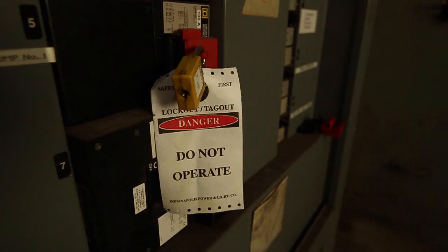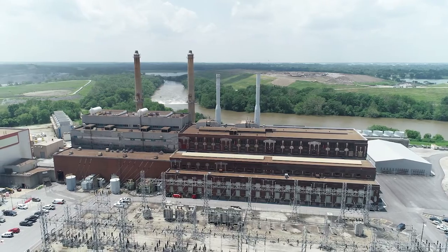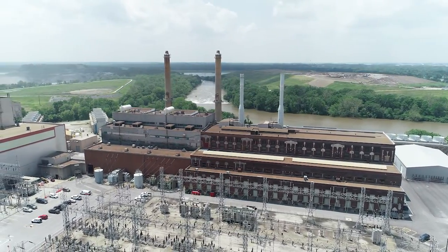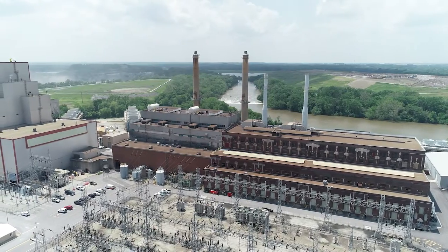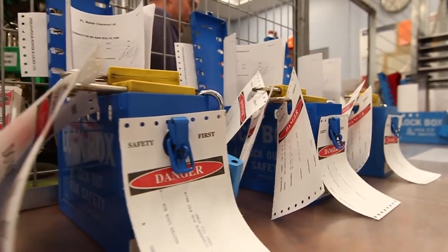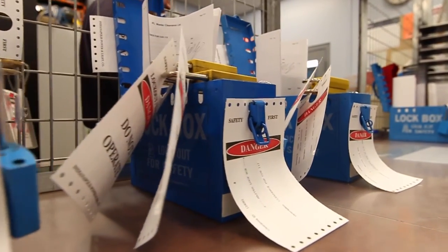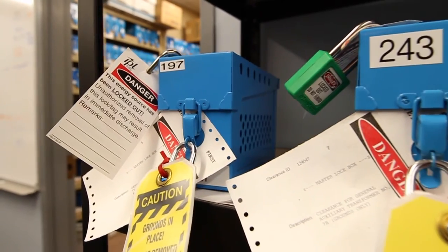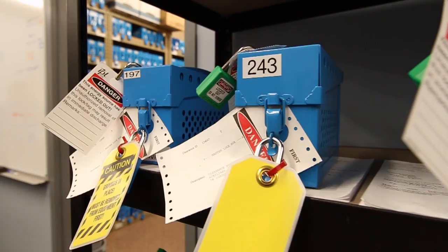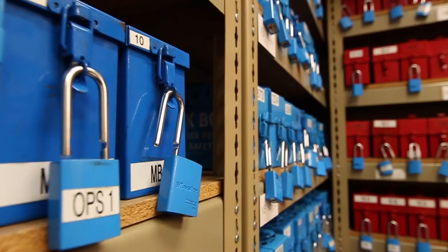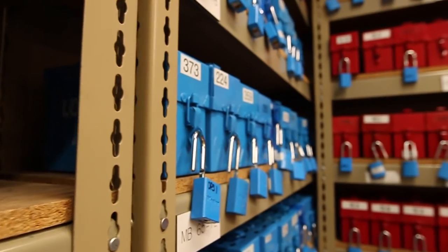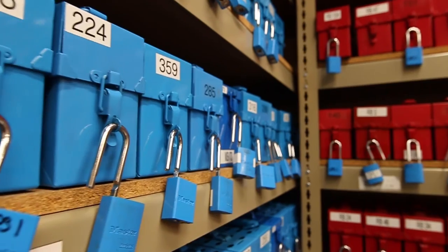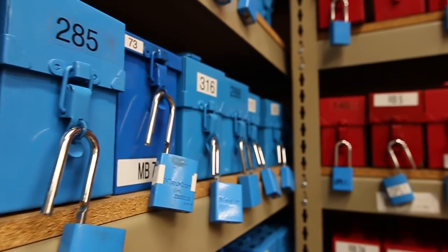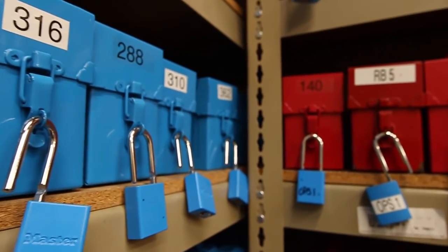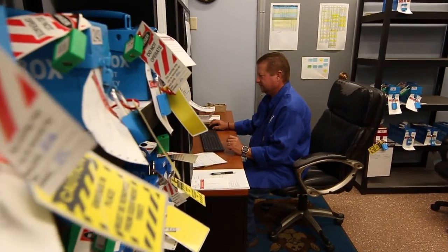Control of energy sources, lockout, tagout procedures. The Harding Street Station Hazardous Energy Control Program is commonly referred to as the Lockout Tagout Program. Additionally, clearance permits are used to track both equipment isolation information and authorized personnel working on isolated equipment. A clearance permit is documentation combined with a method to properly isolate equipment from hazardous energy. It is imperative that communication takes place between IPL and contractors to ensure everyone's safety when working on or around hazardous energy sources. Prior to the start of work activities requiring equipment isolation, the contractor shall request a clearance from the IPL contractor administrator to ensure appropriate de-energizing of equipment.